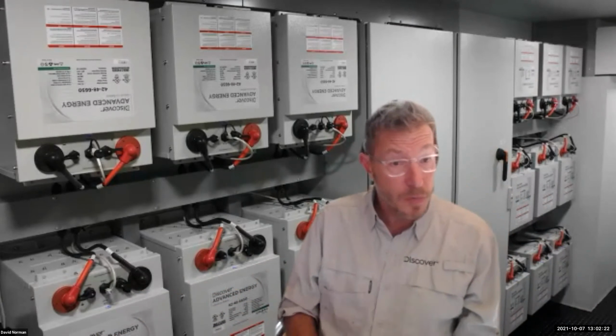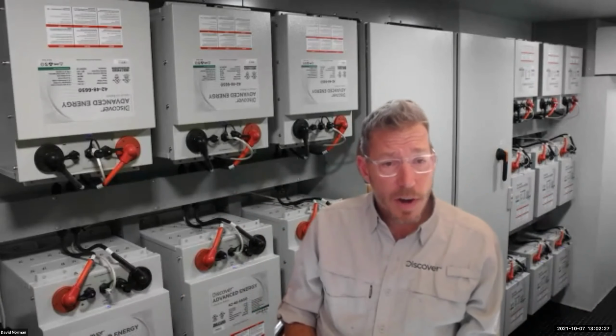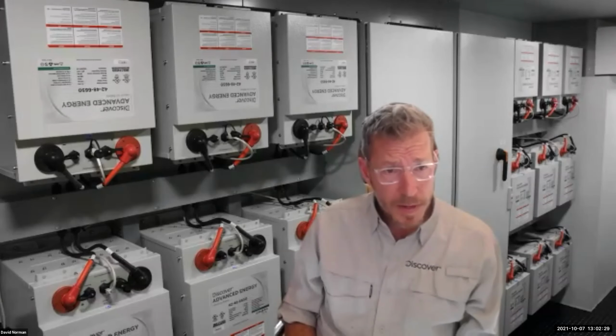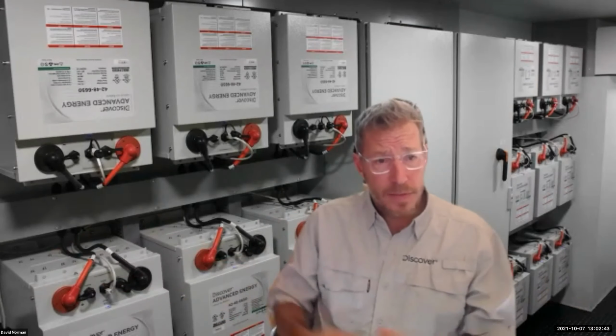The most common way to conclude that you've terminated the network properly, from my understanding, and because we do populate those settings, is that if you know that each of our batteries is 130 amp hours and you have 10 of them connected, when you look on the SCP or through your Insight at the battery capacity rating, once our batteries are plugged in, it should simply read N, the number of batteries, times 130 amp hours capacity. So in this case, 1300 amp hours. And if you've done that, you know your network's terminated.